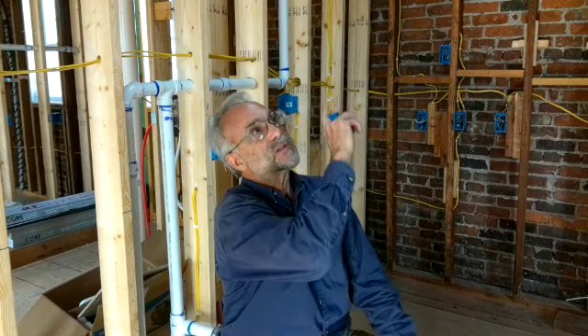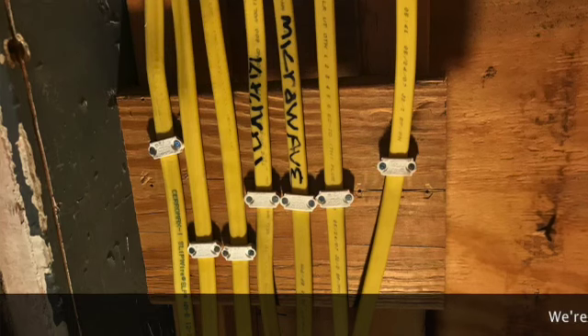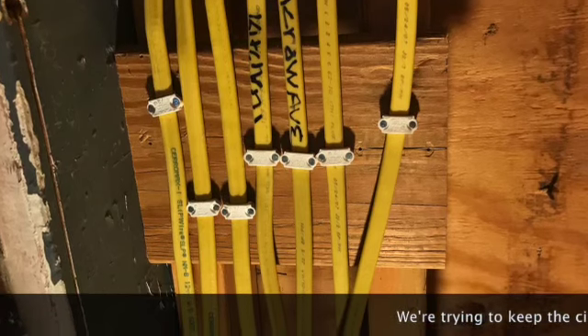And the advantage of this is that if you blow a breaker, if you pop a breaker because something shorted out, and it's the lights that breaker popped, well, then you still have outlets, receptacles, you can plug in a lamp and still see what you're doing, and vice versa. So that way you're not completely taken out of commission if a circuit breaker pops.